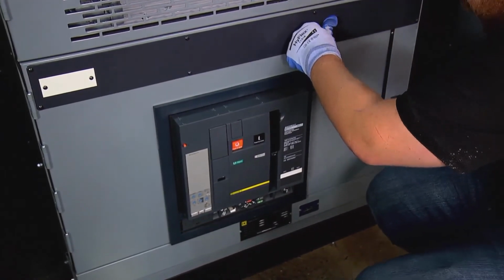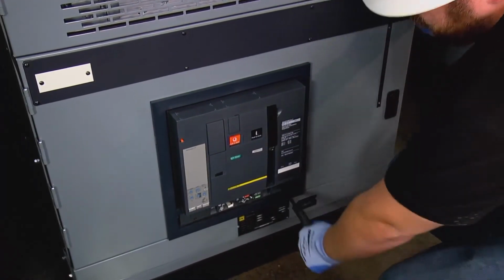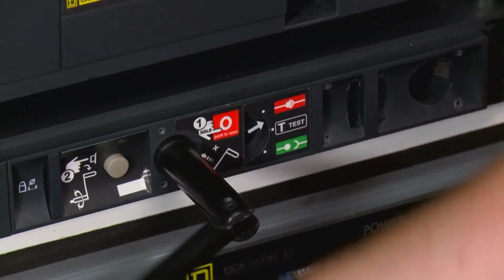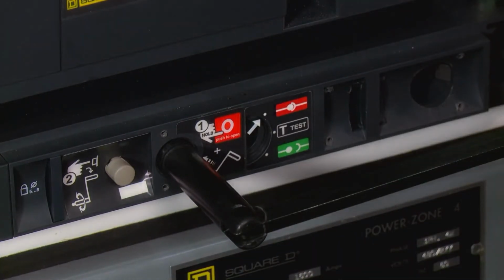Now pull out the racking handle and rack in the breaker by turning the handle clockwise. The breaker is securely racked in once the arrow on the display is in the connected position.